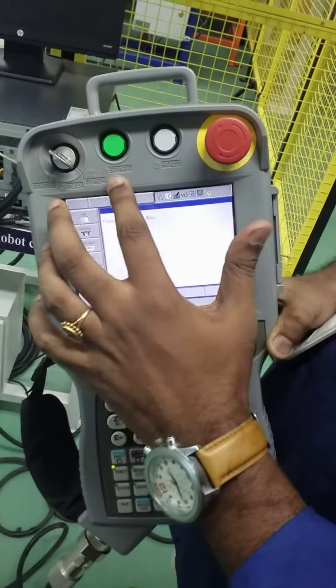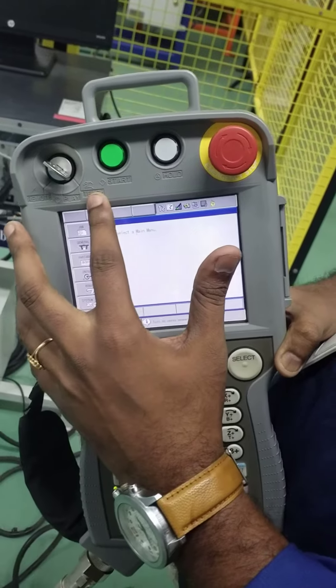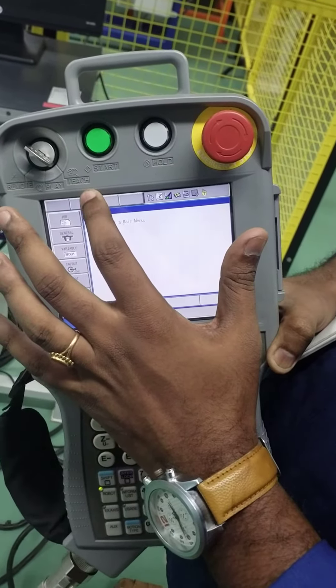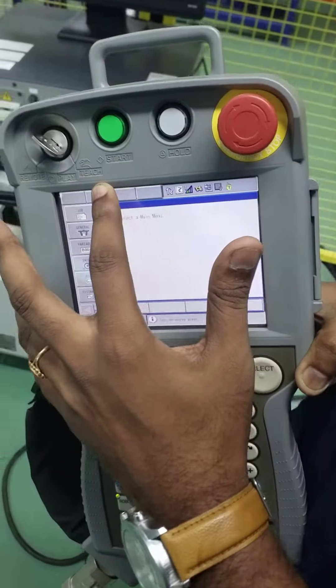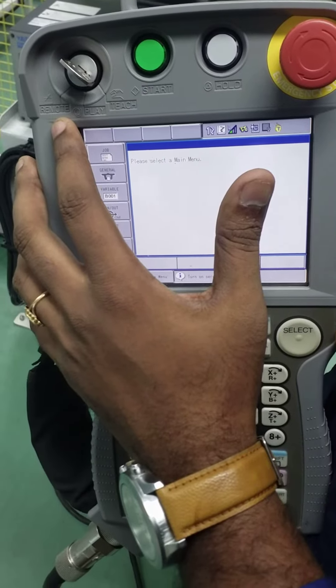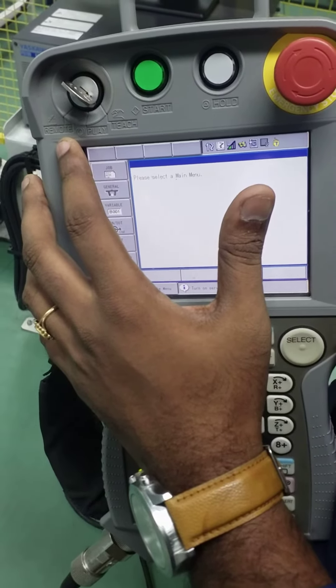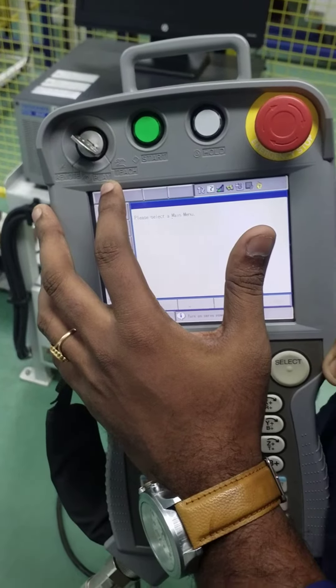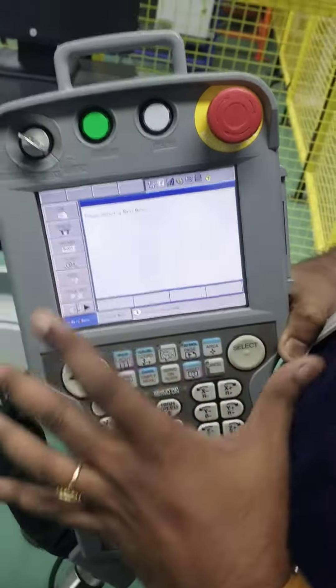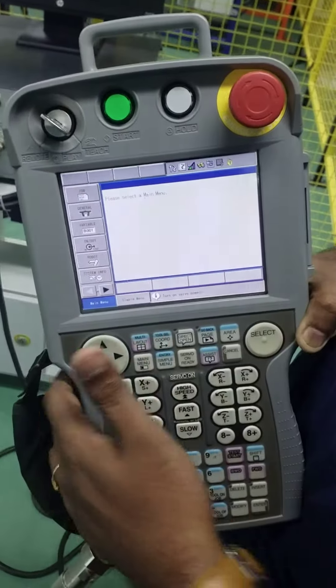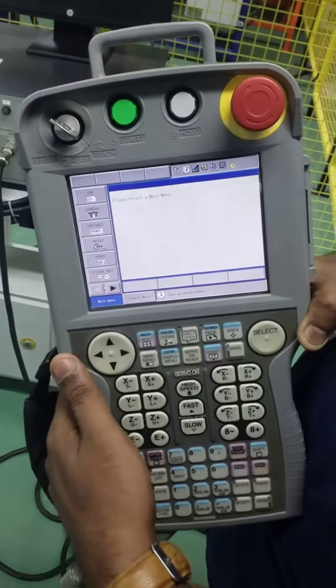On the pendant you have three modes: remote mode, play mode, and teach mode. Teach mode is the mode on which you have to teach the robot. Remote mode is the mode when you give the control to the PLC controller. Play mode is used to play — once the program is programmed, you put it in play mode and when you run the program it will be continuously running.